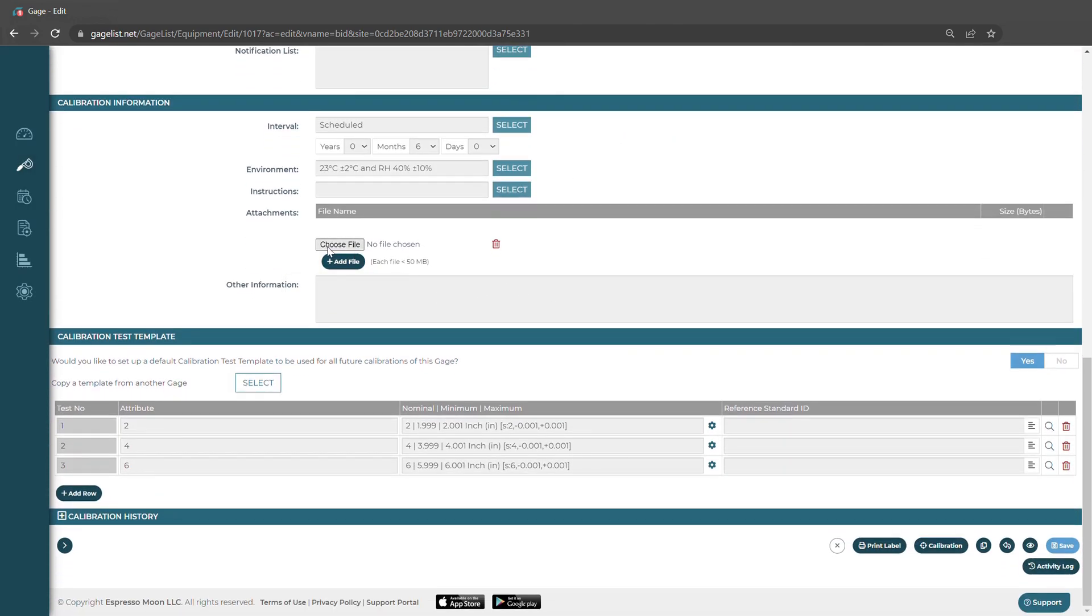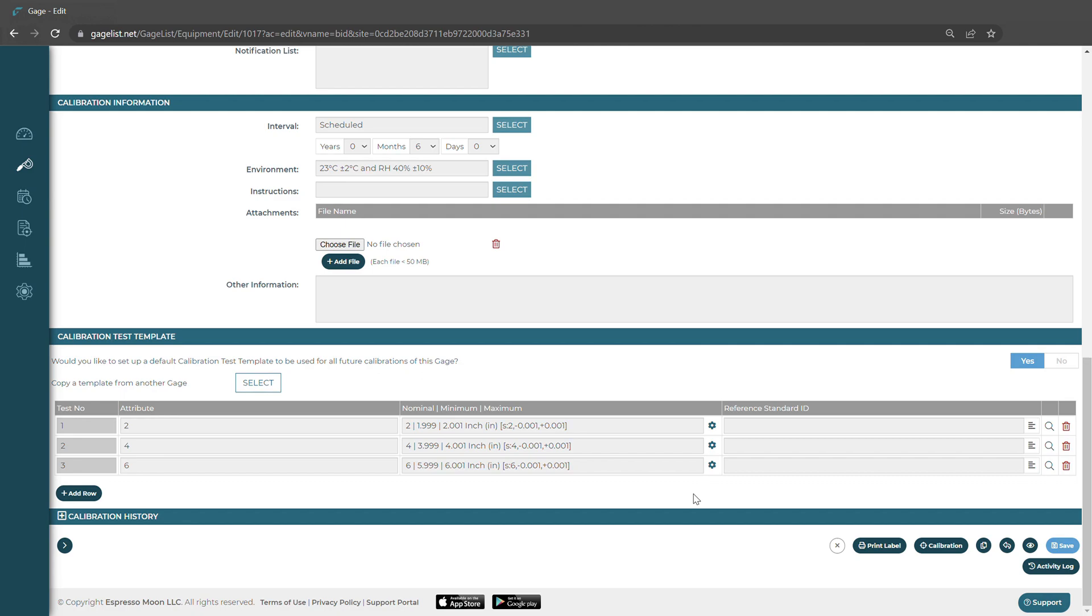We can also upload a file to the gauge record, but we don't want to add our calibration certificate here. We're going to want to do so by adding it in the calibration record section. We also can set up our test template as well. For more information about test templates, please watch our video on how to set up a gauge record.